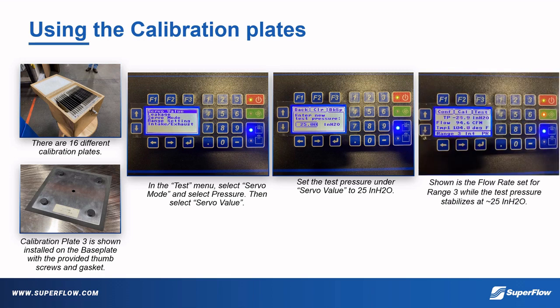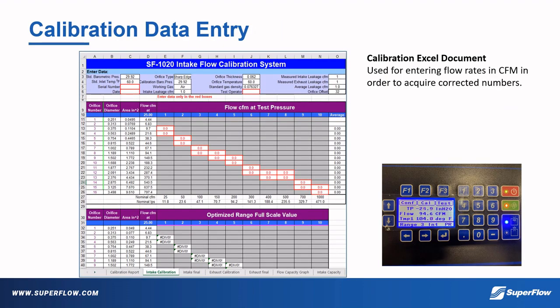Back on the main menu, we can see the bench is being flowed and a test pressure of 25 inches H2O is stabilizing. The flow rate is shown as 94.6 CFM and the temperature of the motors is 104 degrees. After an orifice plate is flowed in a particular range, the flow rate needs to be recorded in the calibration Excel document. Shown along the bottom are the sheet tabs used depending on the type of calibration being performed.